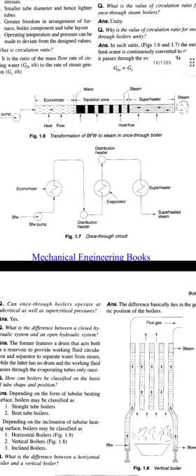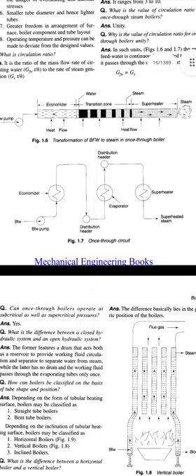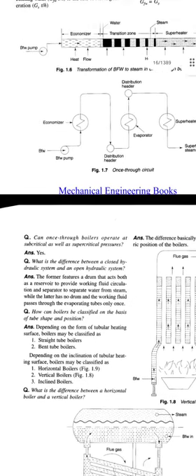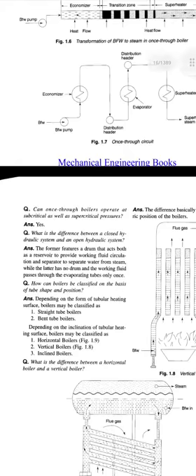The once-through boiler circuit is shown in the second picture. It shows the feed water pump feeding water to the economizer. Through the distribution header, the evaporator is next, followed by the superheater. The outlet is superheated steam. This is the once-through boiler.